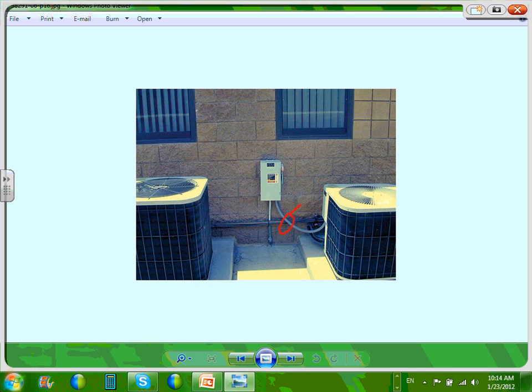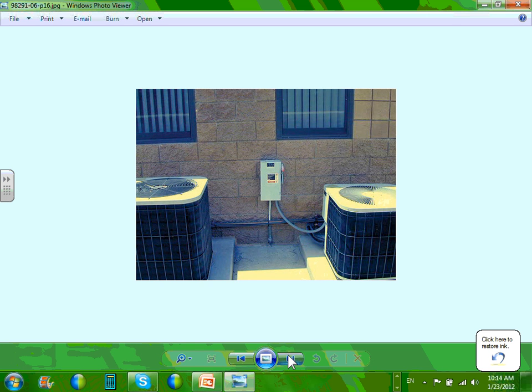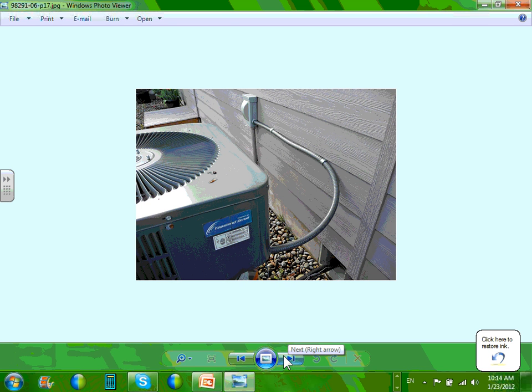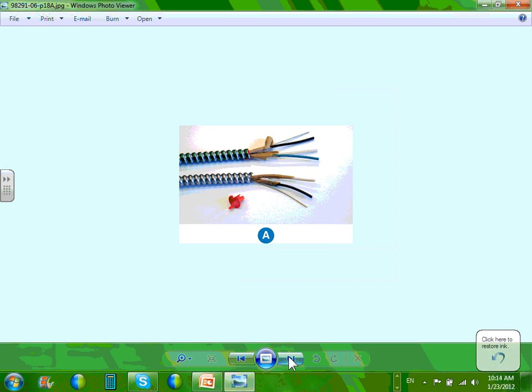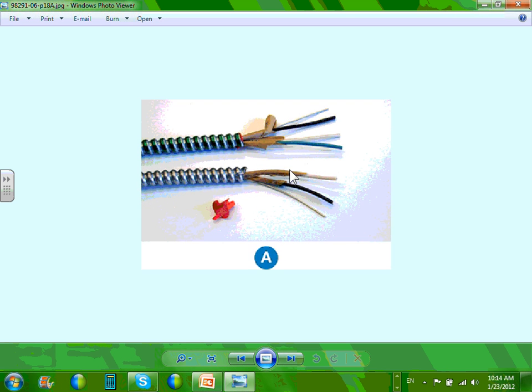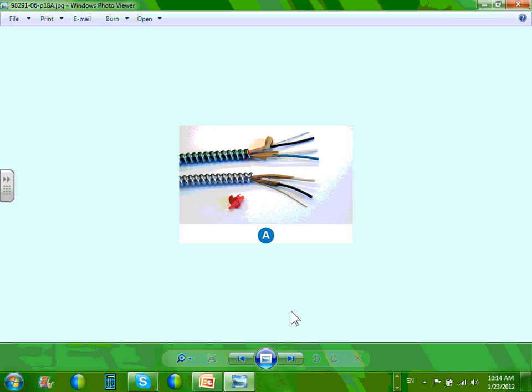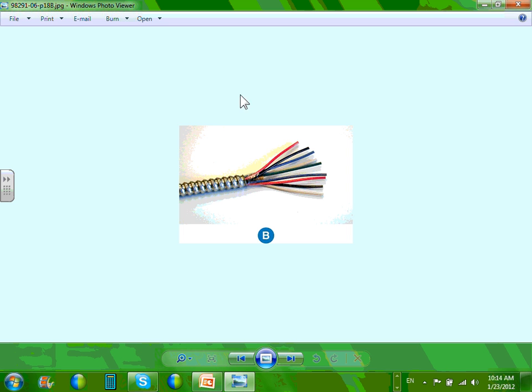Had this been in a dry location, the only thing that changes is that you don't have to use liquid tight. You can use flexible metallic conduit, not liquid tight. You don't have to if it's indoors. Here's another picture of it. This is just a couple of pictures about MC and AC cable, guys.